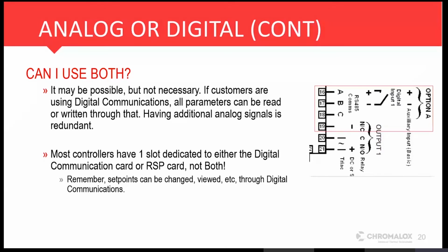And I have got this question before too. Can I use both? So if a customer is, let's say, using Modbus and they want to send a remote set point, should they do it through analog or should they do it through the digital communications? Well, most of our controllers, you can't even set it up to have analog and digital. Occasionally, I think there are some builds where you might be able to pull that off, but the question is why you would want to. It's really basically a redundant feature.